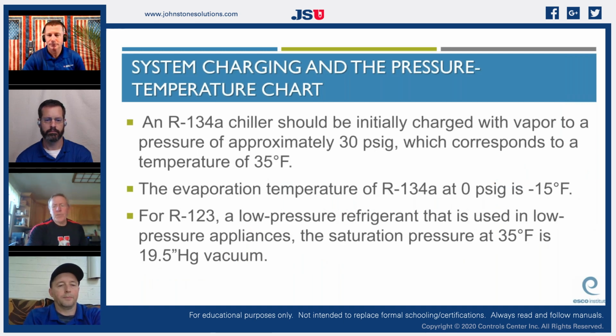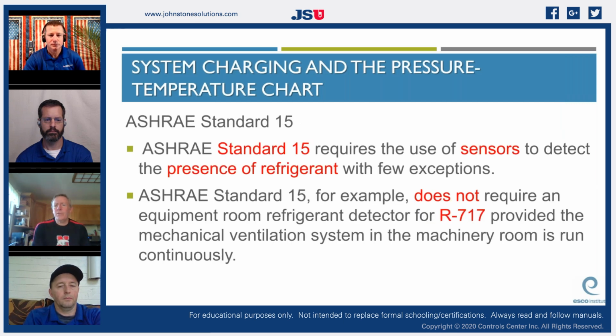And then I'm not going to spend a lot of time on that. ASHRAE Standard 15 requires the use of sensors to detect the presence of refrigerant, with a few exceptions. Some commercial buildings and big maintenance rooms have some of these sensors in there that will actually bring on an evacuation system or a mechanical ventilation system. In some rooms with 717, which is that ammonia? Yeah. Okay, R717 is ammonia. Some of these are always ventilated. So you have to be careful. I actually had a friend that had some problems because they were doing some brazing in a mechanical room.